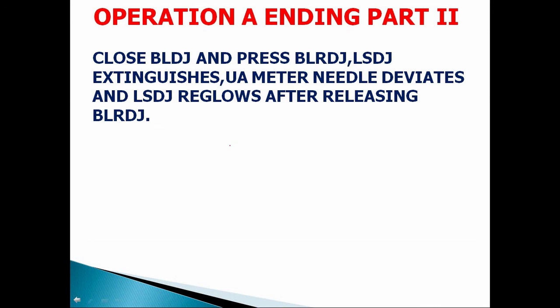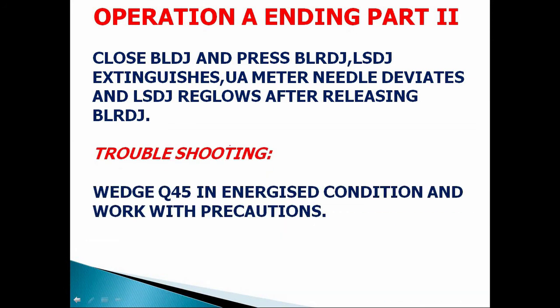Close BLDJ and press BLRDJ. LSDJ extinguishes, UA meter needle deviates, and LSDJ reglows after releasing BLRDJ. It is same like operation B part 2. After releasing BLRDJ only, LSDJ reglows. The reason, our troubleshooting procedure is wedge Q45 in energized condition and work with the precautions. Reason is Q45 normally open interlock on empty DJ branch is defective.